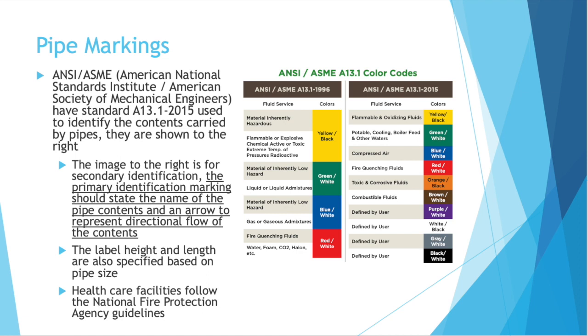Pipes used in industry to convey fluids should be marked with the contents of the pipe. In America, ANSI and ASME — the American National Standards Institute and the American Society of Mechanical Engineers — have standard A13.1 2015, used to identify the contents carried by pipes. The primary identification marking should state the name of the pipe contents and an arrow to represent directional flow. The color of the marking and font can also help identify the contents. For example, a green label with white font indicates material of inherently low hazard, while a yellow label with black font means the material is inherently hazardous.